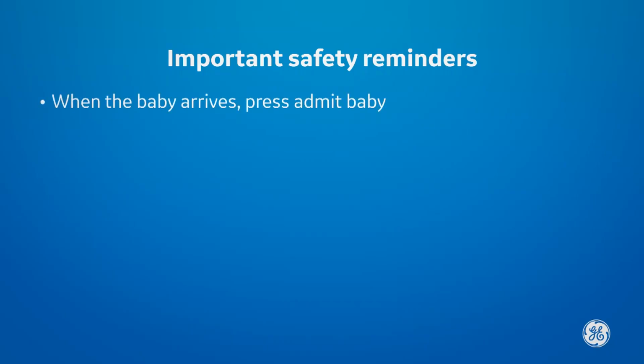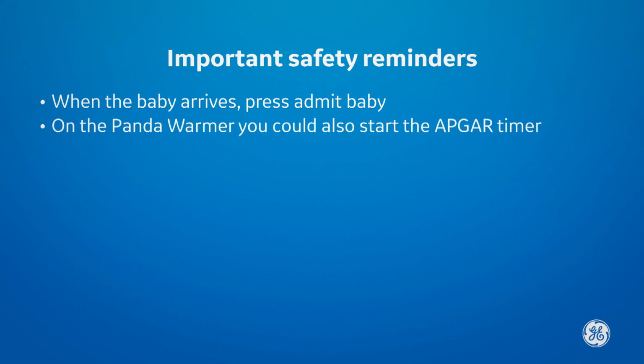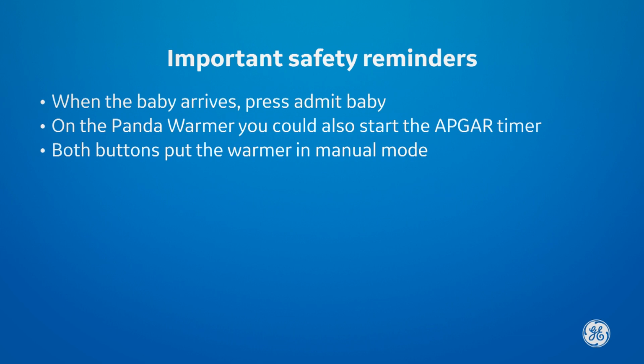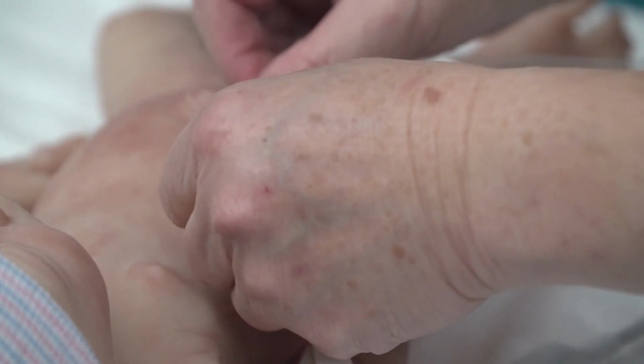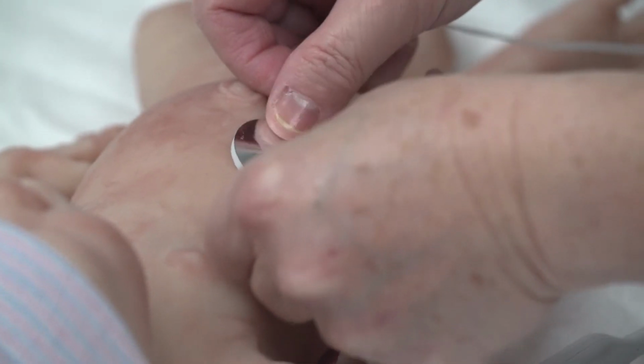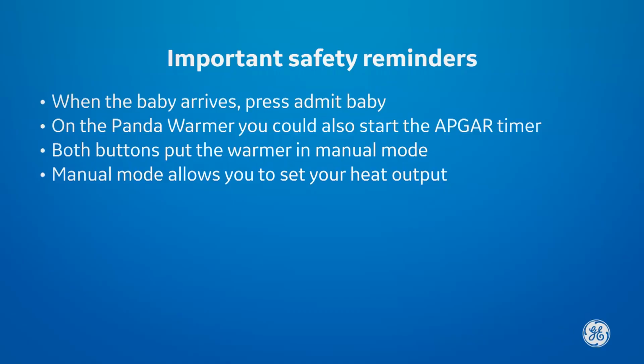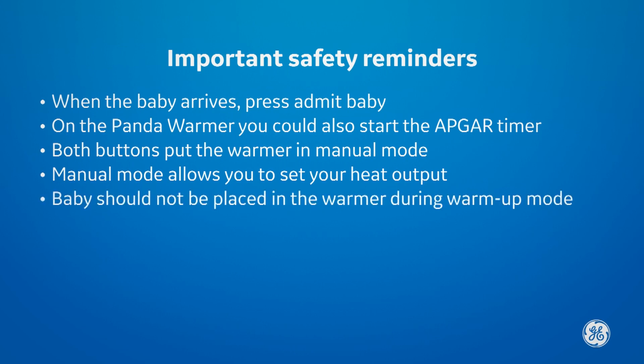Again, when placing a baby in the bed, you should press the Admit Baby button. On the Panda warmer, you can press Admit Baby or start the APGAR timer. Both buttons put the warmer into manual mode and allow you to set your heat output. Per hospital protocol, place a skin temperature probe on the baby and switch to baby mode, or continue to monitor the baby in manual mode. Again, the baby should not be placed in the warmer during warm-up mode.